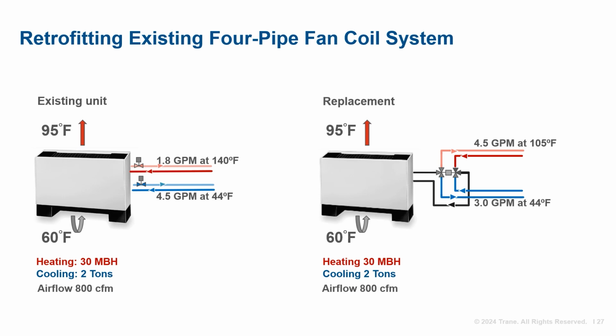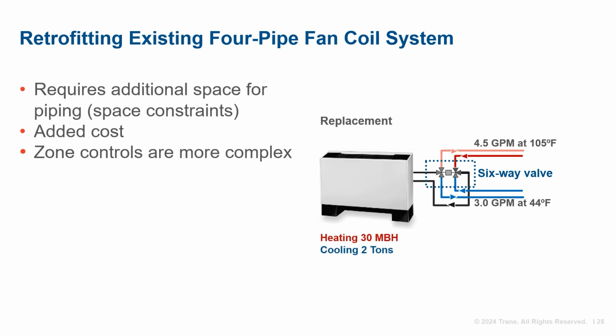One available option is a 6-way control valve. This will allow for the coil to be used for either heating or cooling. However, this requires significant space to accommodate both the piping and the valve. It also adds additional cost to the retrofit. One 6-way valve is more expensive than 2 2-way valves and zone controls. Plus, it's more complex.